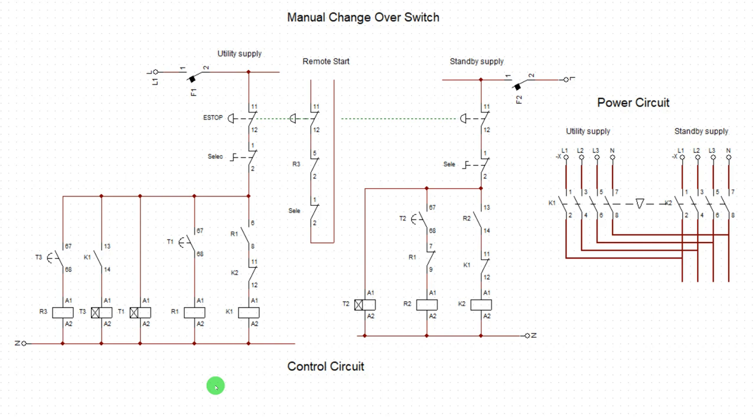But if the genset does not have cooldown duration, you now integrate this part to enable the genset to cool down for some minutes, either 1 minute. At least 1 minute is okay. That 1 minute is to enable the oil because in heavy duty generator, once you start it, oil will have to lubricate the system. So that oil and the frequency and the speed can stabilize. If you don't do that, in no distant time, all the mechanical components will wear out, will begin to damage.